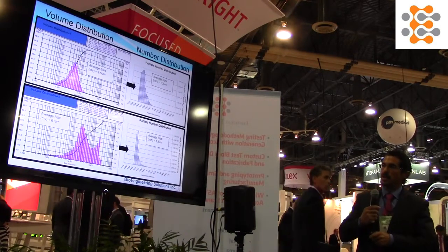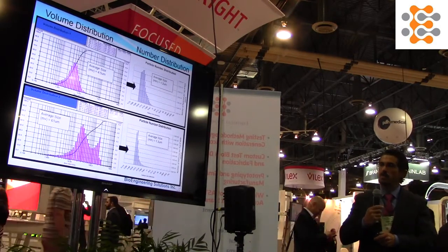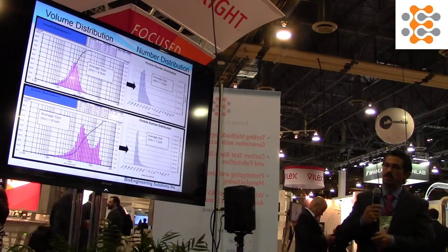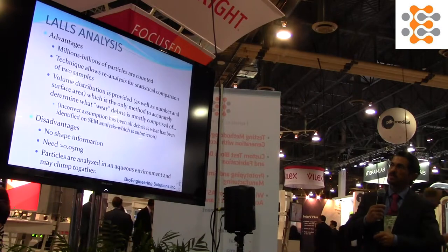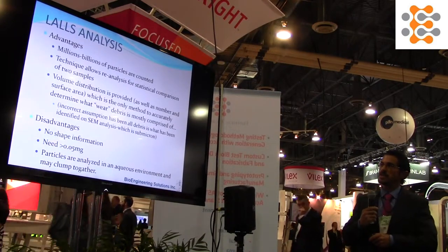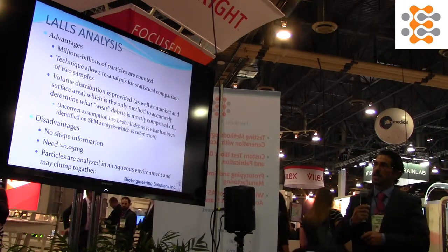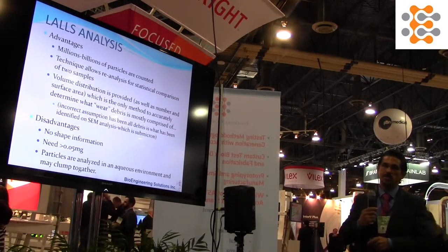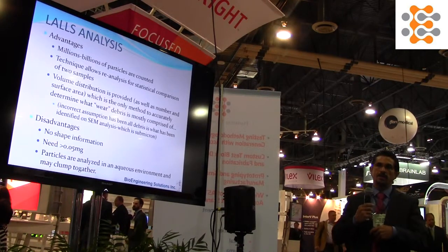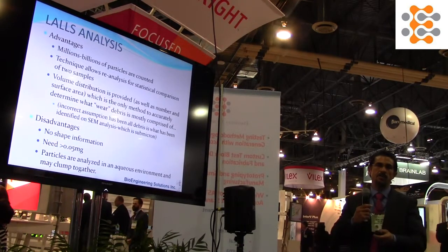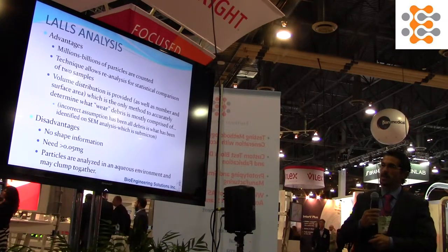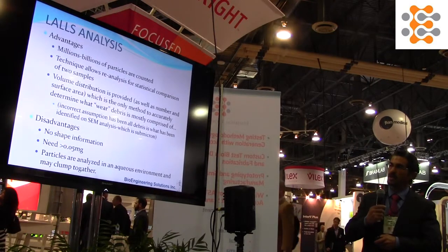A volume and a number distribution should really both be reported when it comes to implant debris, even if it's only hundreds of particles backed out of an SEM analysis. The advantage of LALLS is the millions to billions of particles that are counted. The technique allows for reanalysis and gives you a volume distribution, which is certainly not accurate in an SEM analysis due to the lack of counting millions of particles — you can't find that one-in-a-million very large particle that you would see on a LALLS analysis.